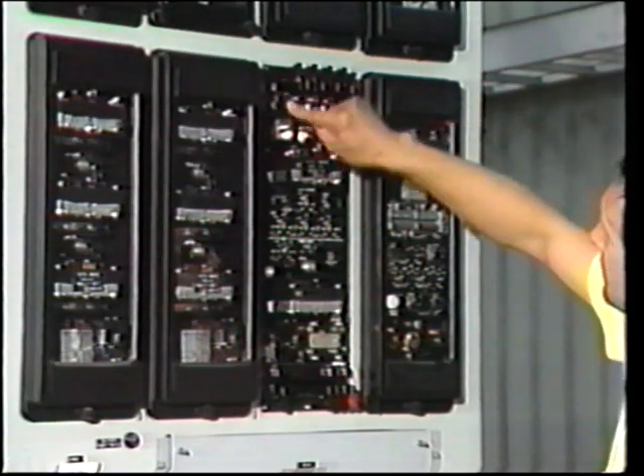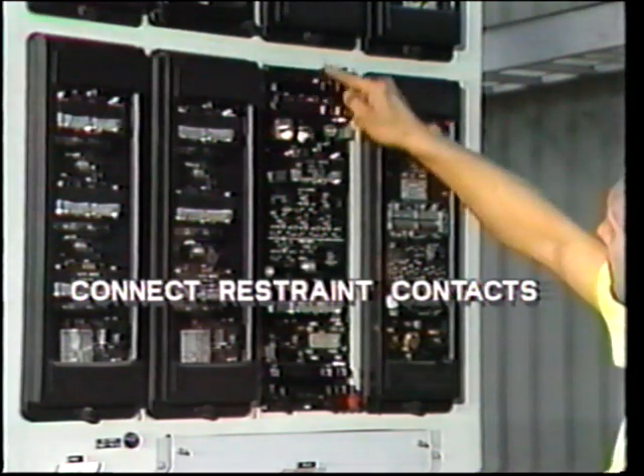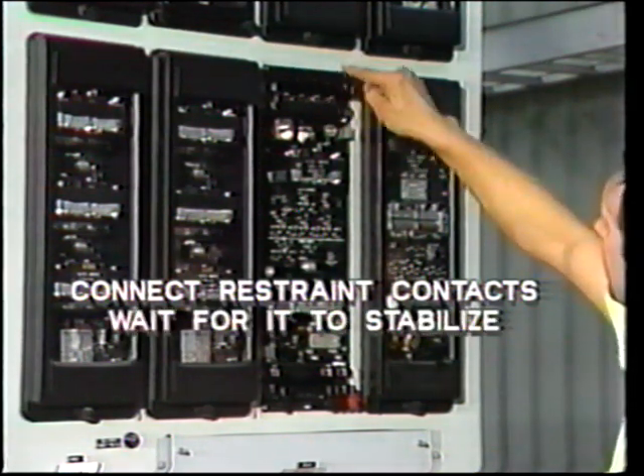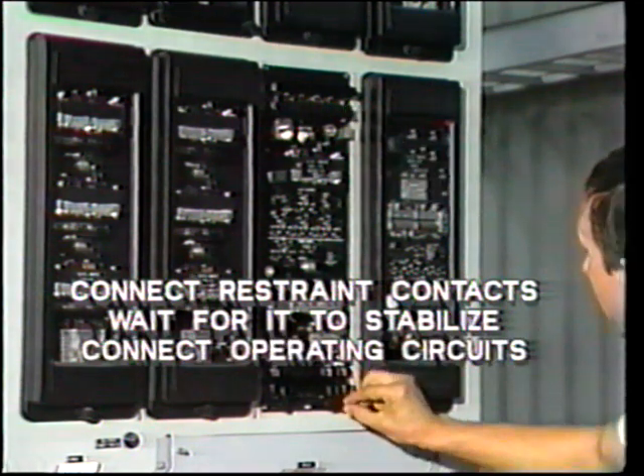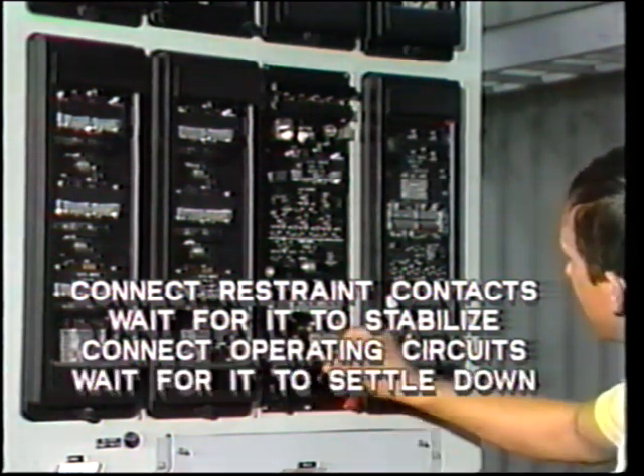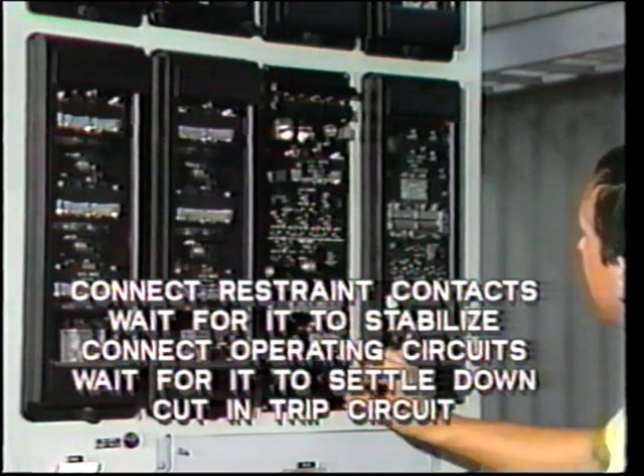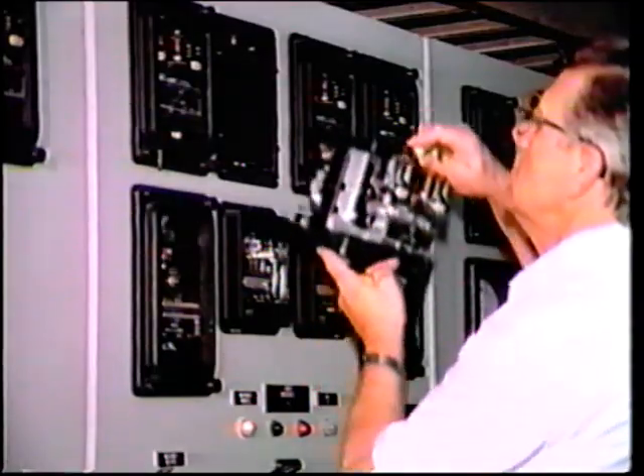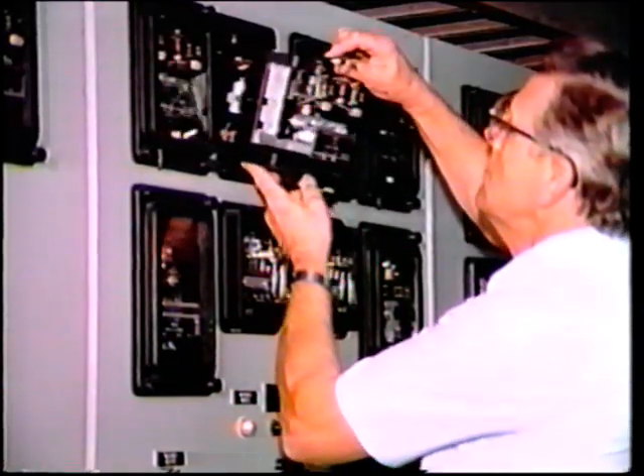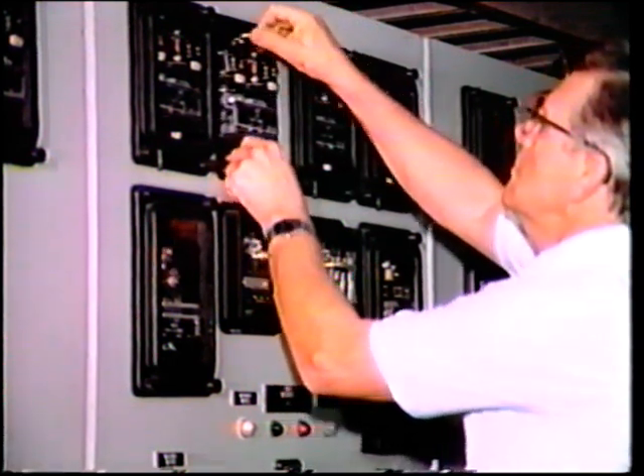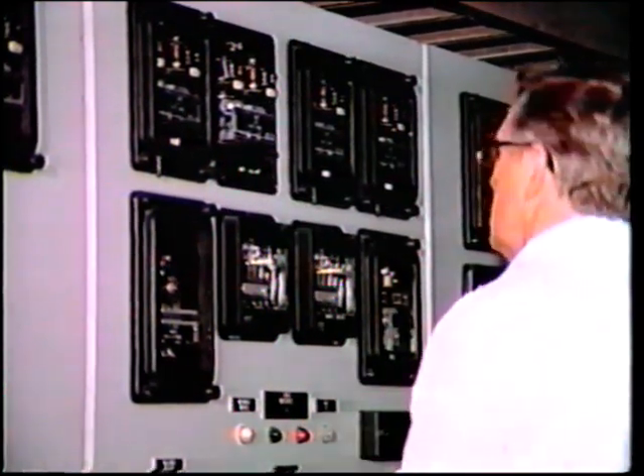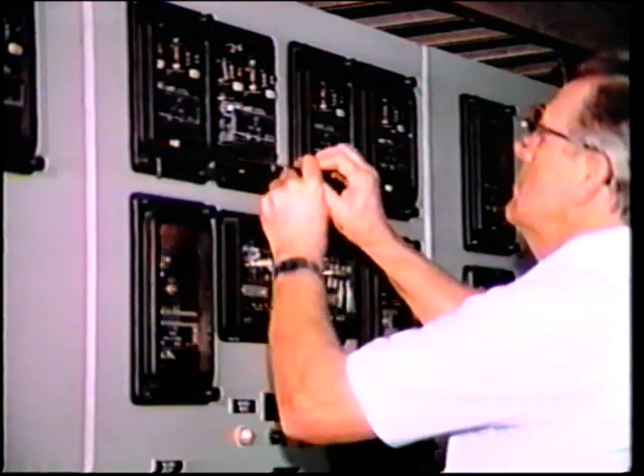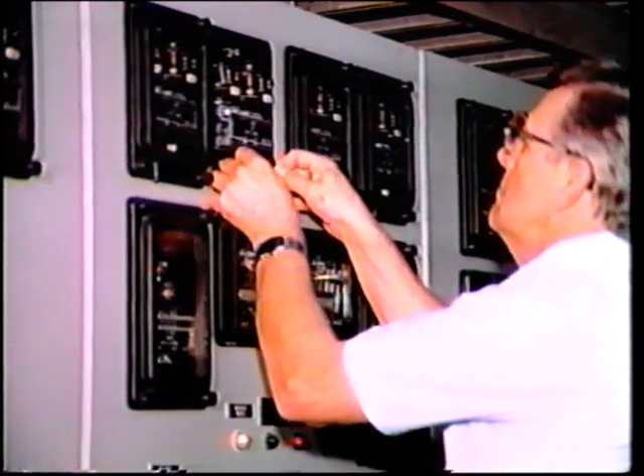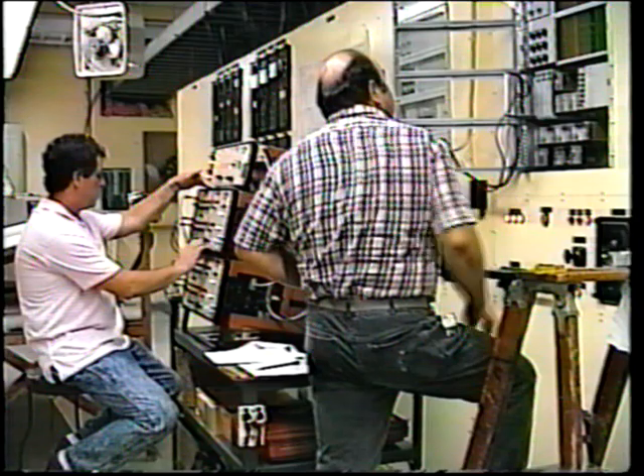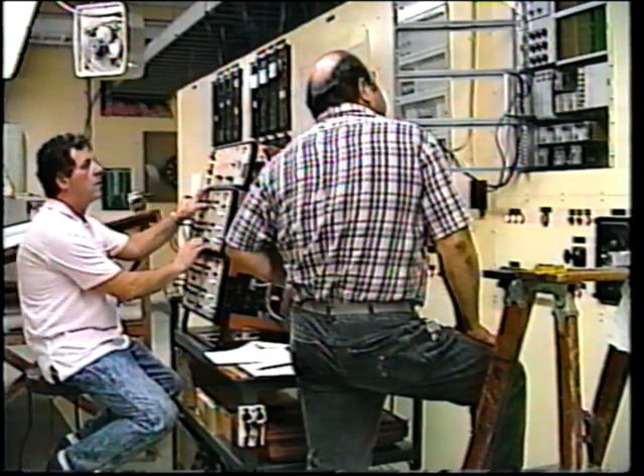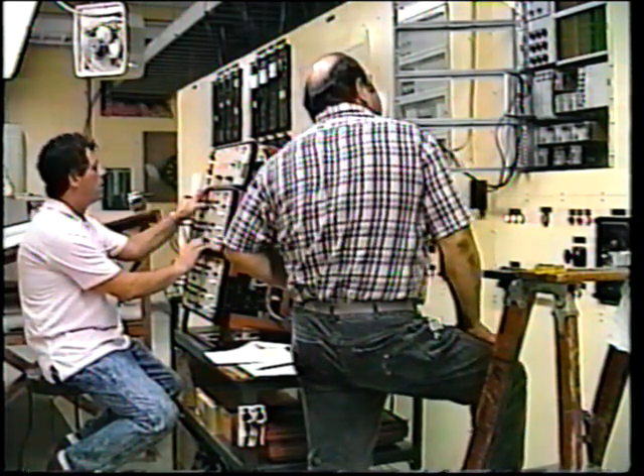Where appropriate, remember to connect the relay restraining contacts first, wait for it to stabilize, then connect its operating circuits next, wait for it to settle down, and finally cut in the trip circuit. Similarly, when replacing an under-voltage relay, insert the connecting plug very slowly so that the long fingers contact first, or hold the contacts open to block false operation. Inadvertent tripping can and does occur during routine tests. Let's look at an actual incident.